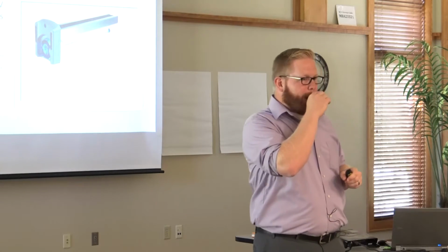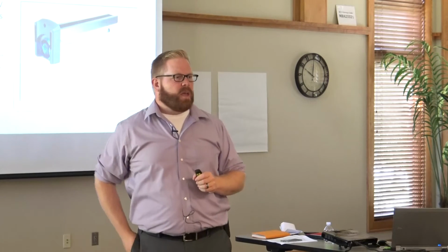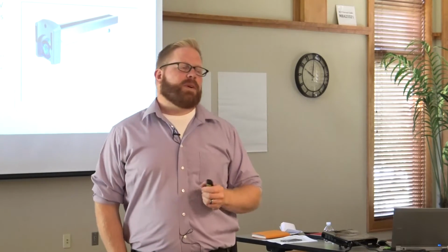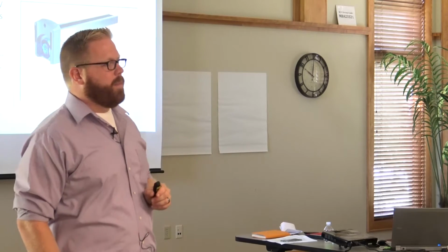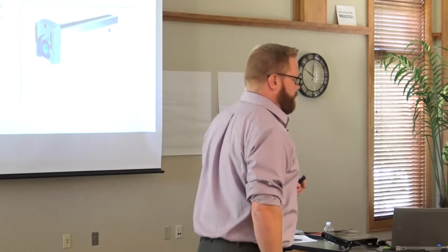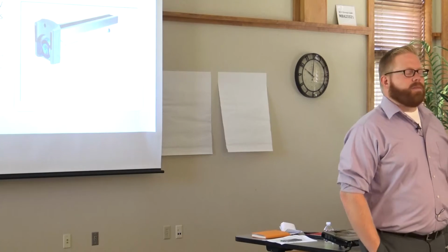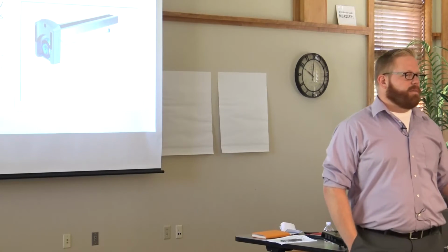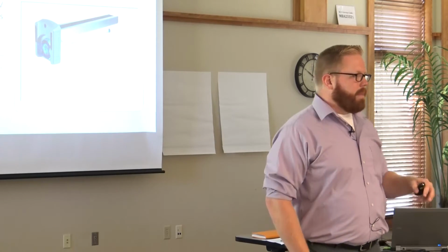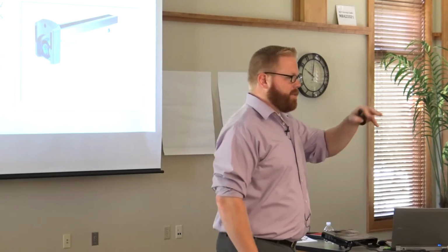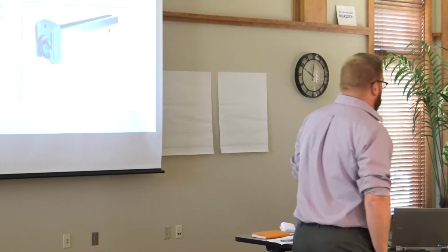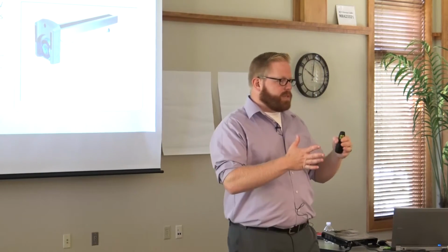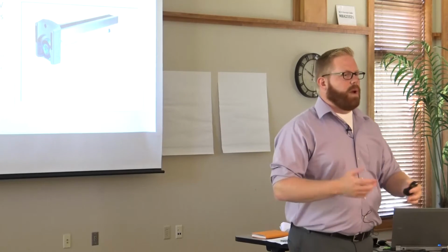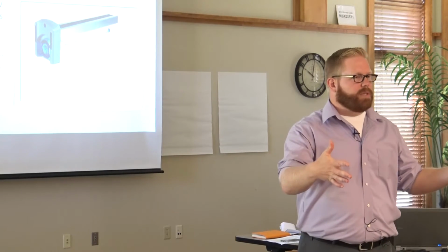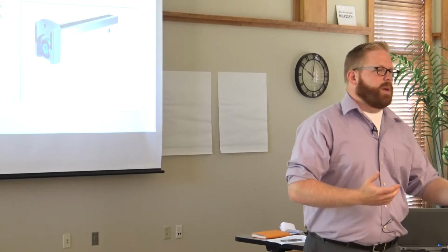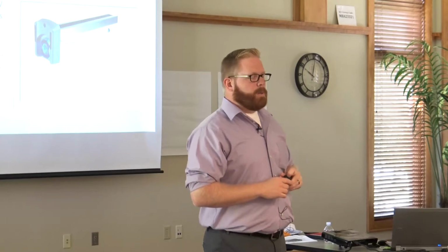Yeah, when you say Manual J calculation, is that the same thing as, I think of, the REScheck? It's very similar. It's a different program. A Manual J calculation is typically provided by a software program like Wrightsoft, or Elite, or ACCA, Air Conditioning Contractors of America. But yes, that Manual J calculation is similar to a REScheck or a REM/Rate. Basically, it's taking the full BTU load of the house to determine what piece of equipment you need to install.